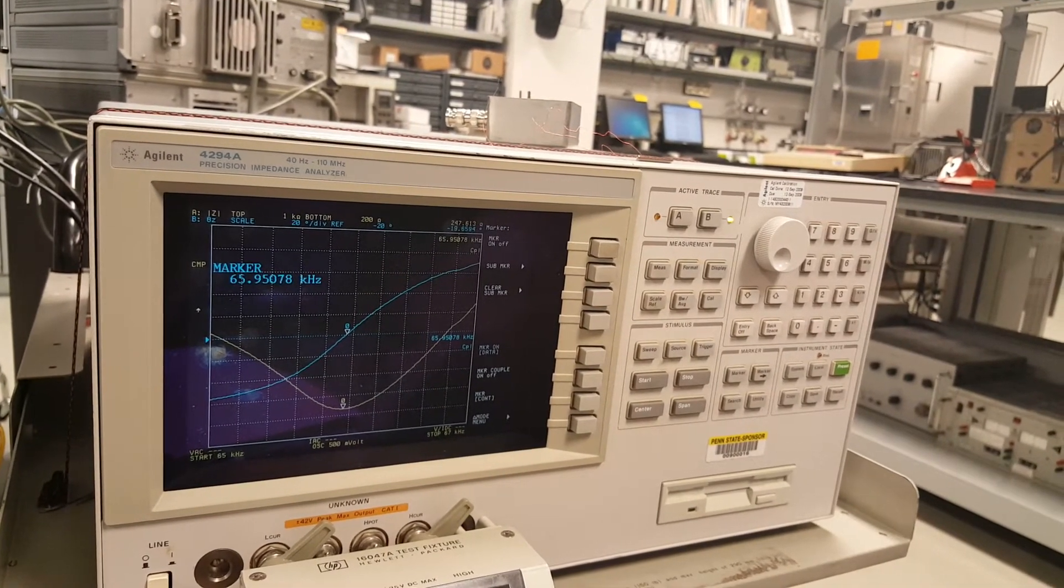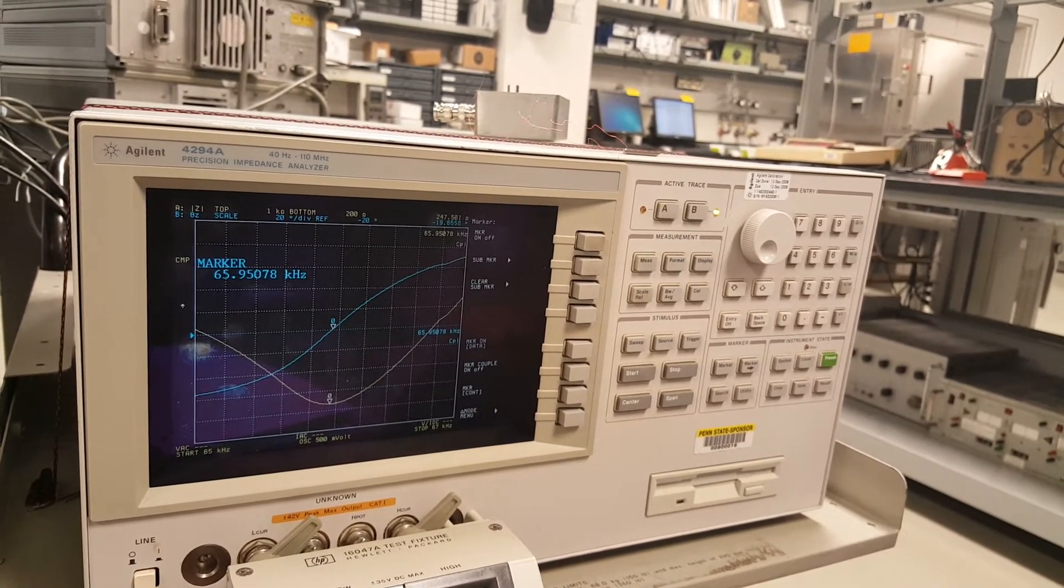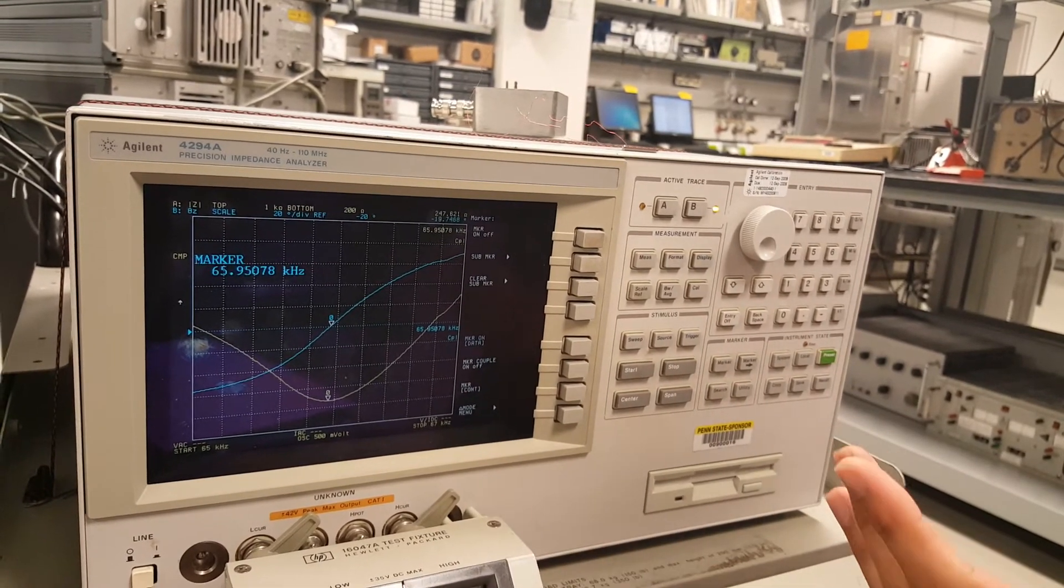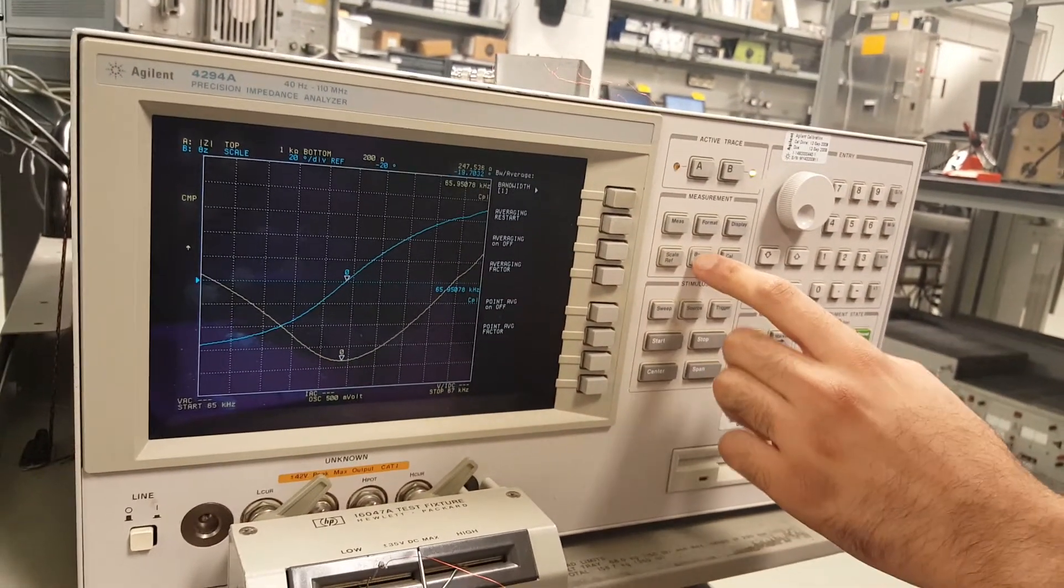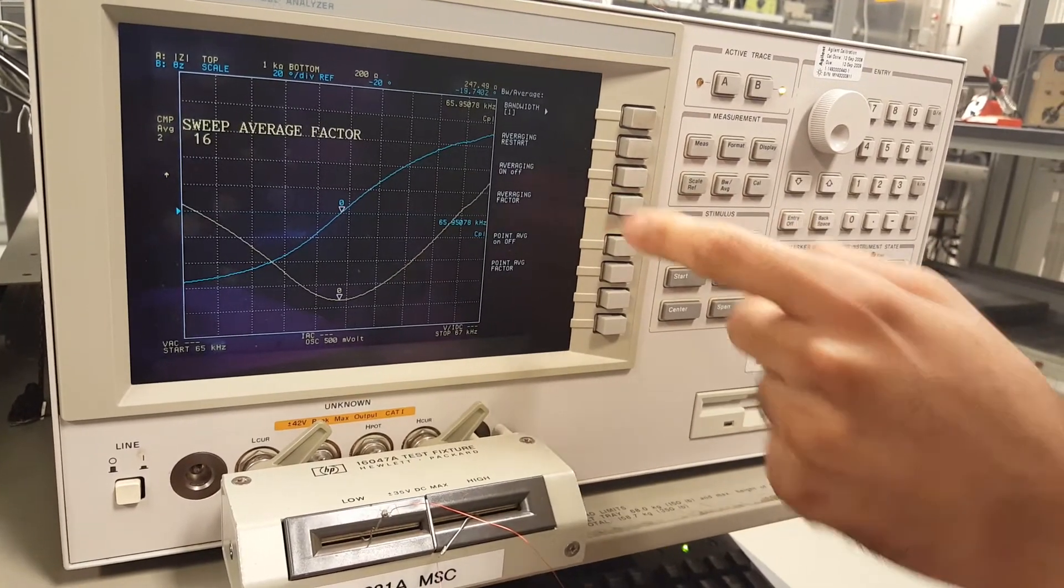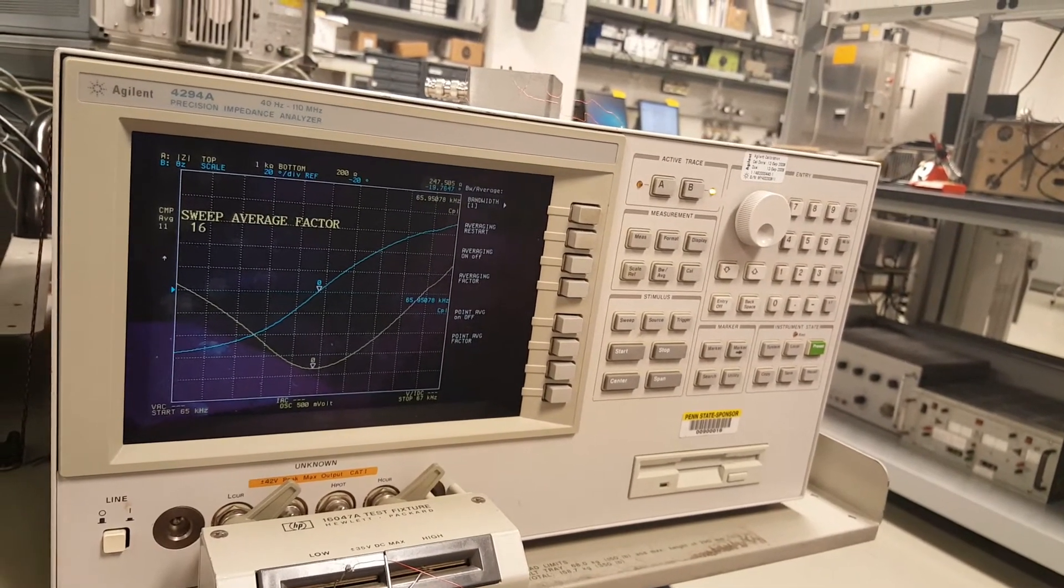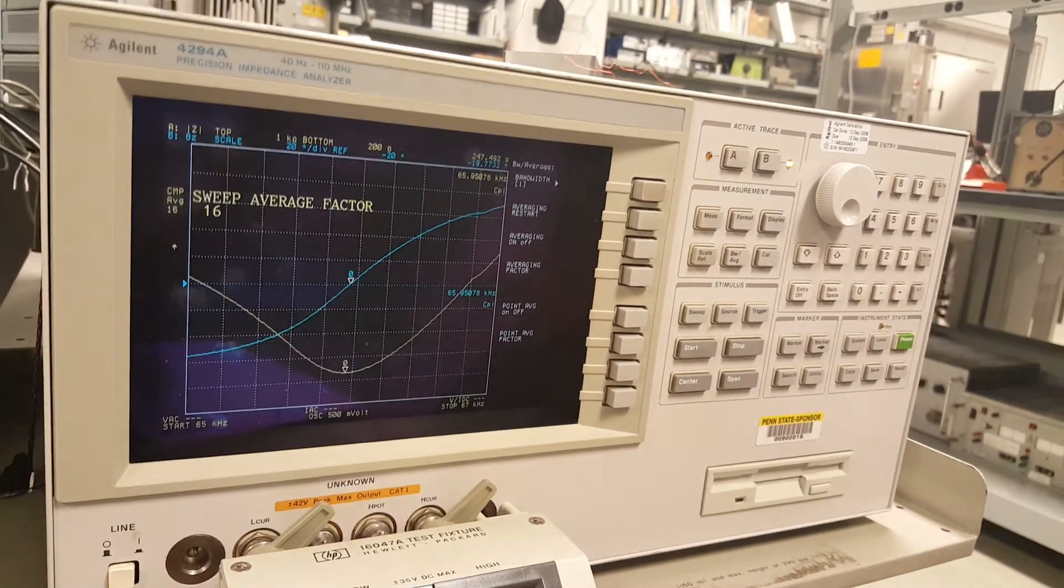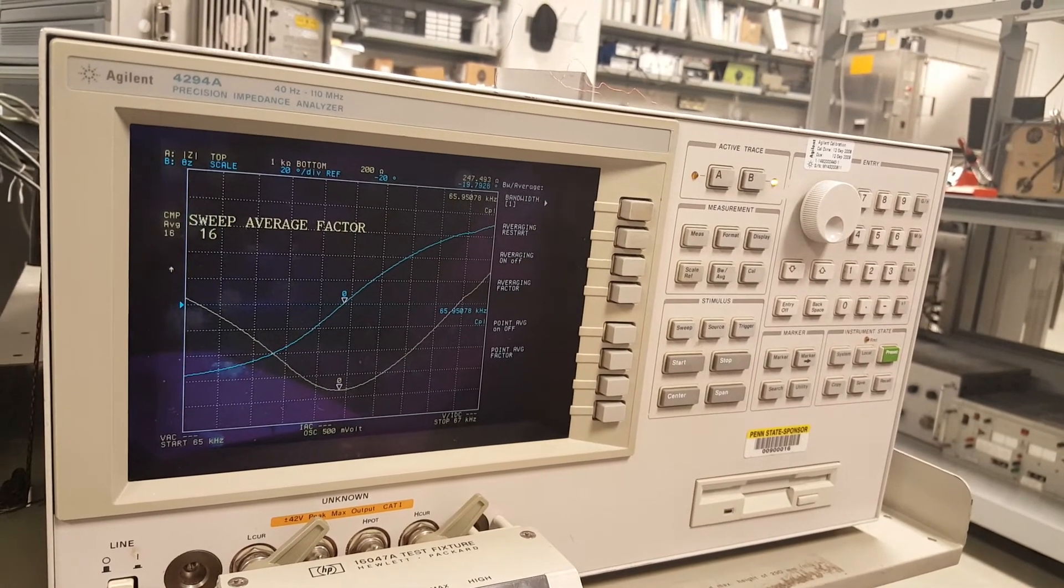There's a lot of things built in this machine that help you measure more accurately. And for piezoelectric materials which have a large transient response, it's many times important to take into consideration some of the things which this can do to make the measurement slower and more accurate. One of the things is using this averaging. Right now averaging is off. We can turn averaging on. We can turn averaging on and now we're going to look at the averaging factor. It's at 16. So basically it measures the thing 16 times. Each point, it measured 16 times, it takes the average of that each point, and then it plots it. This makes it go slower, it makes the sweep go slower, which also in turn makes the transient response less. If you have a transient response, you may be getting different errors.